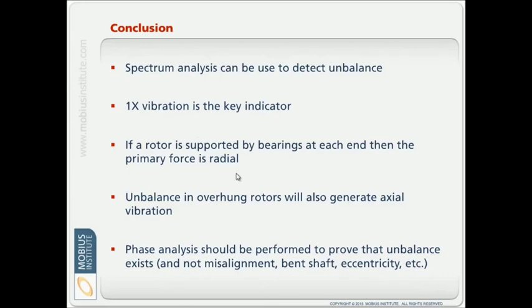So we can look for that 90 degrees phase relationship and we can compare the vibration at either end. If it's an overhung rotor, then we expect to see the axial vibration as well. So between the spectrum and phase readings, we get a good diagnosis.